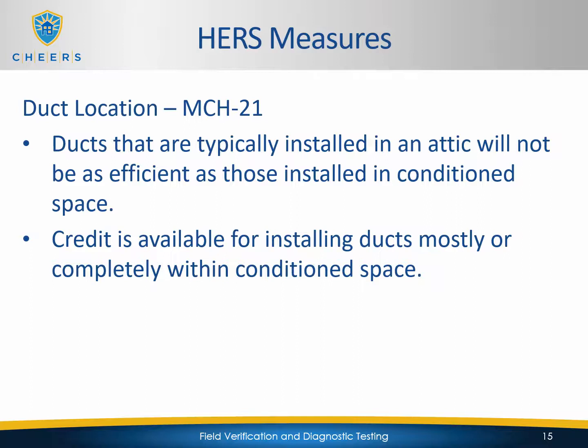So the duct is going to be insulated. And so if you can put a duct into a location where the temperature is more close, if there's not as much of a delta T in temperature, then you're not going to have as much heat transfer, and so it's going to be more efficient. So duct location deals specifically with locating ducts in spaces that are better suited for minimizing that heat transfer.